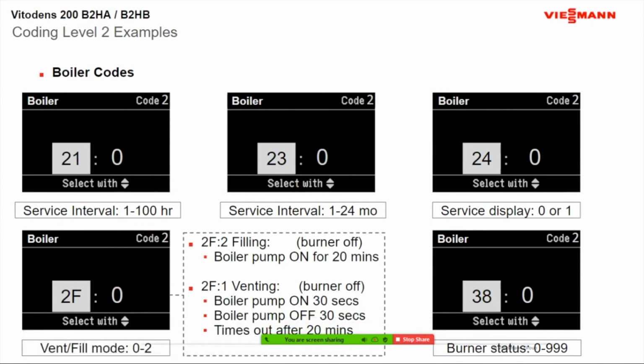And then on address 38, I always like to tell the guys that are doing troubleshooting on this boiler, if you go to address 38 under boiler, there should always be a 0 there. If you look at the last page of your fault codes on this boiler, they give you 5 more fault codes that do not display. So if you go to address 38 and you had a 3 here, this is one of our boilers that doesn't give you a fault for a flow. So if you see a 3 here, you now know you have a flow issue to this boiler, whether your pump's not working or your flow switch is not working.